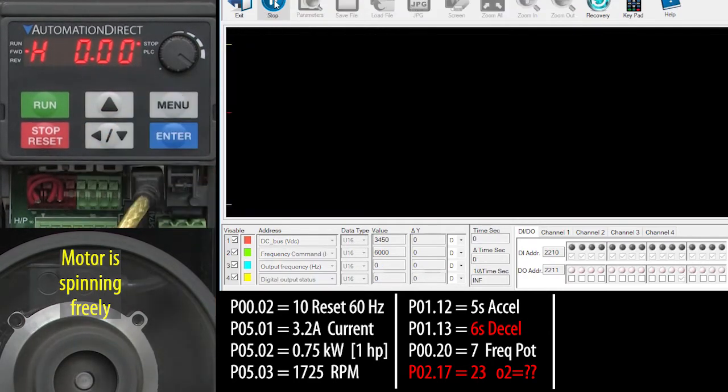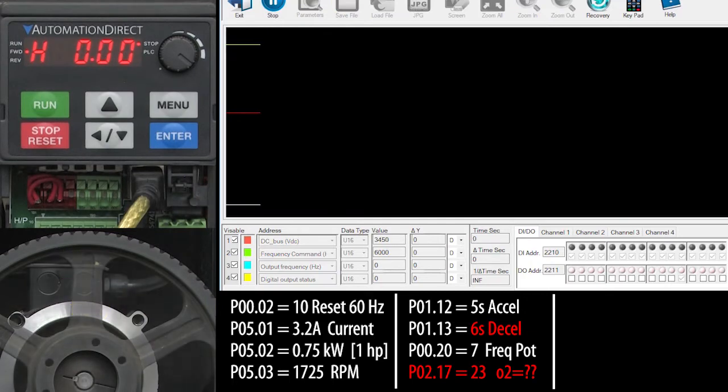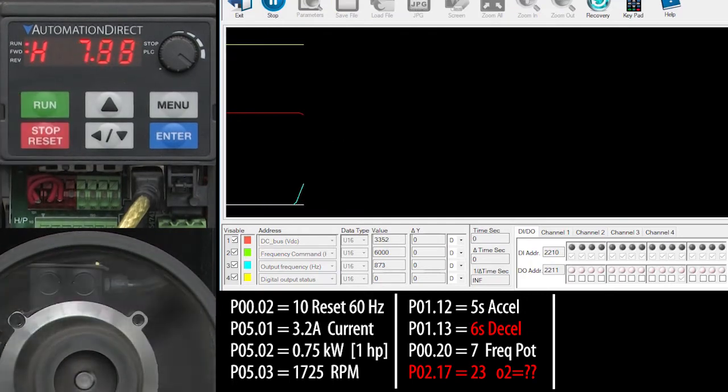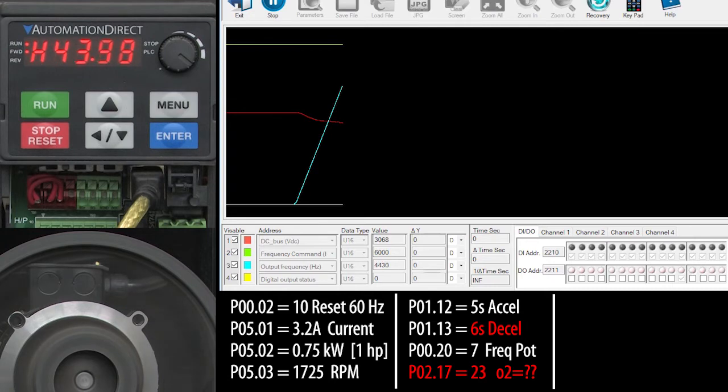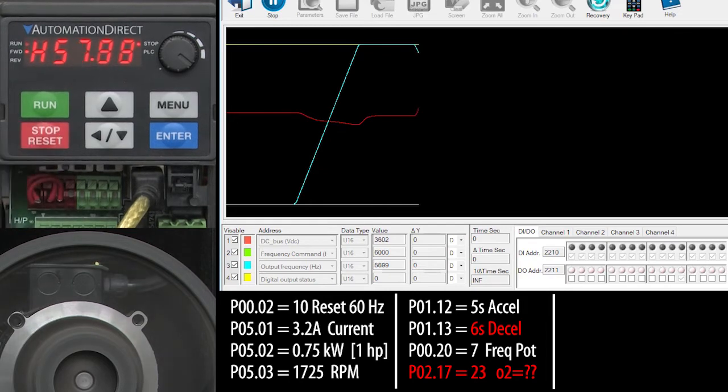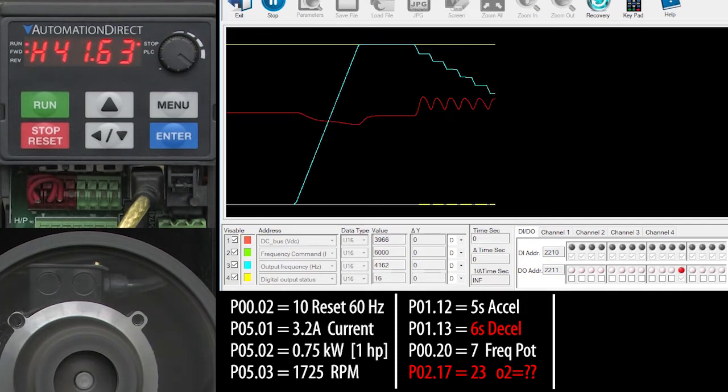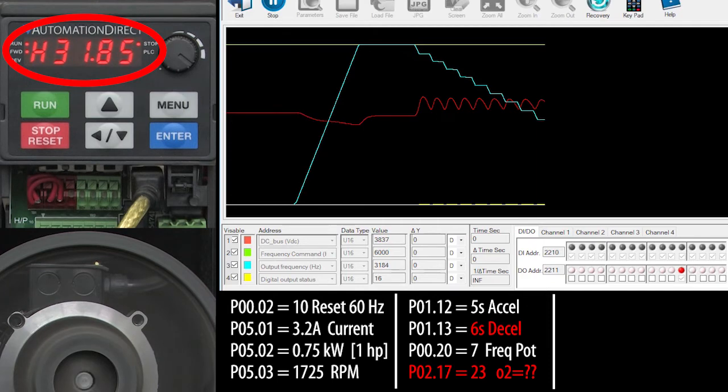I'll start the scope and hit run. Let it ramp up, wait for the DC bus to settle out and hit stop. Hmm, this is taking a lot longer than the 6 second deceleration time we asked for, isn't it?